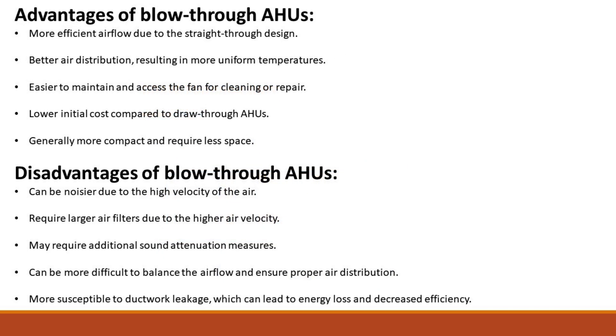Advantages of blow-through AHUs: more efficient airflow due to the straight-through design; better air distribution resulting in more uniform temperatures; easier to maintain and access the fan for cleaning or repair; lower initial cost compared to draw-through AHUs; and generally more compact, requiring less space.